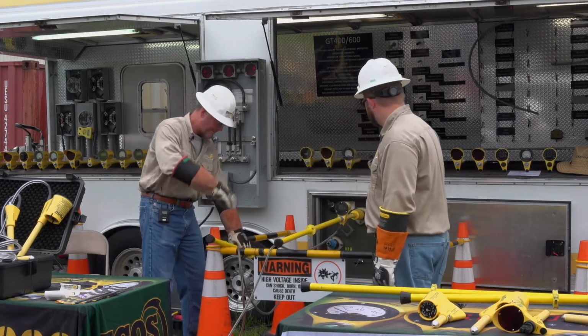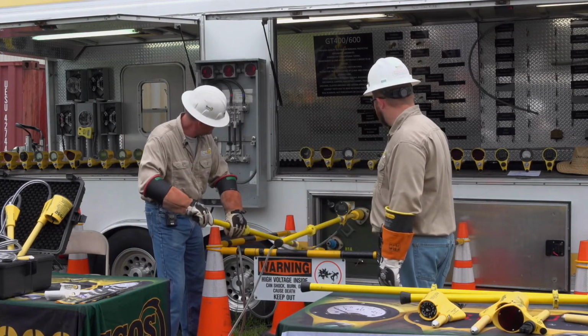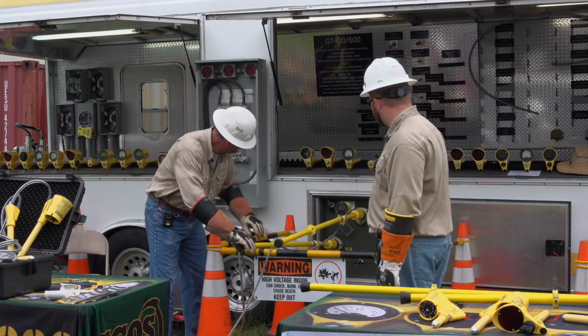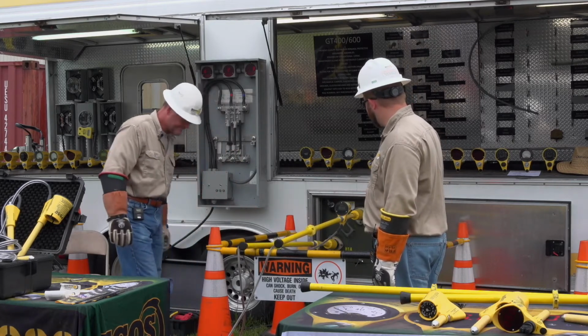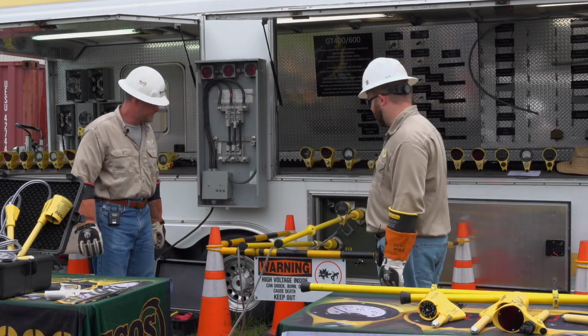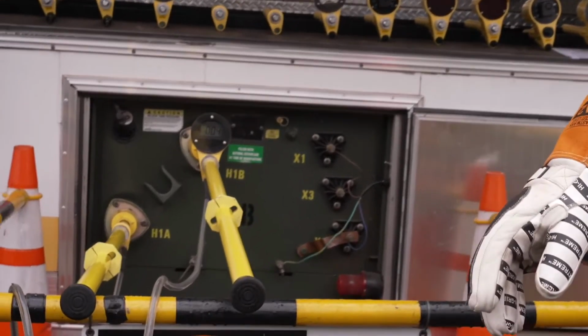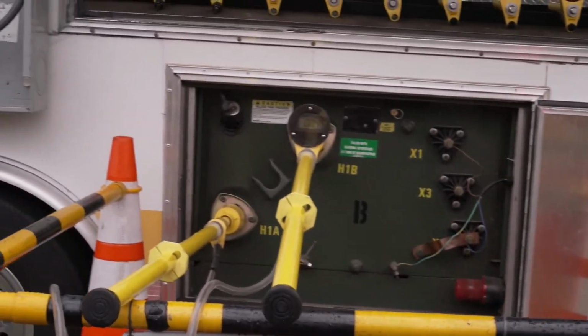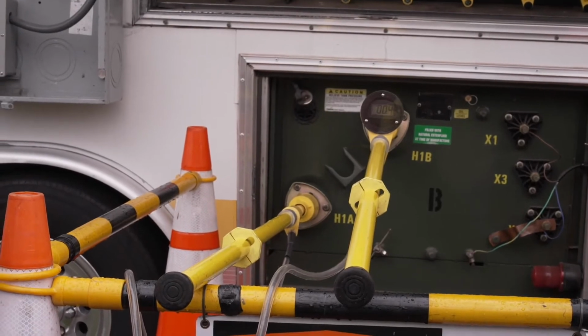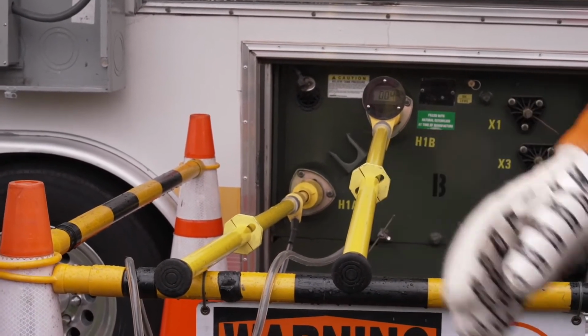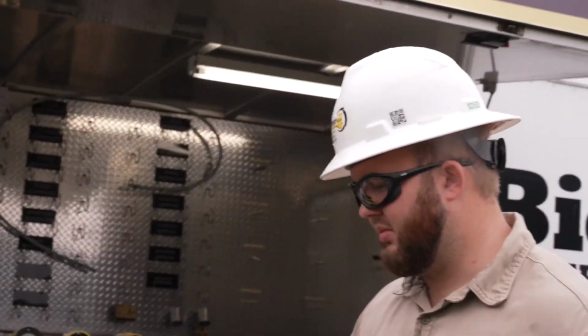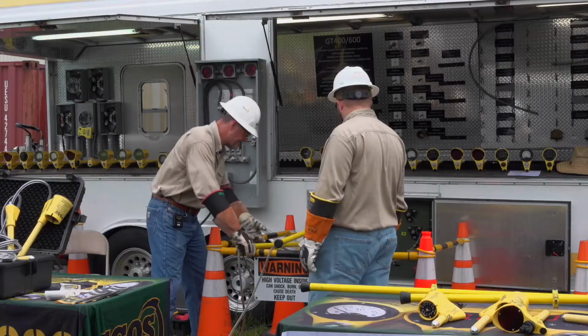So go ahead and tell them what I'm going to do, Ryan. Now we're going to go to the other bushing. If we see 0 or close to it, we know we're in phase. Here we see 0.4, very close to 0. That's just the cable bleeding on this wet grass. On a dry day, maybe working on rocks, you may see 0 itself, but here we see a little bit of that bleed in the cable, so we see 0.5, 0.4.